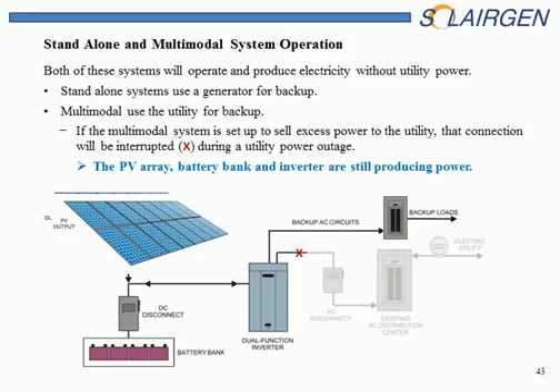So if you see that it's an interactive system when you come up to the structure, then you isolate that it's either microinverters or a string inverter with a PV optimizer on it or not. If you don't see any of that, then you start thinking, is there a battery system? And you look for a plaque that indicates that there is a battery system in place. And if you don't see that, there's still the possibility that there is one. Just because it hasn't stated that there is doesn't mean that there isn't one.